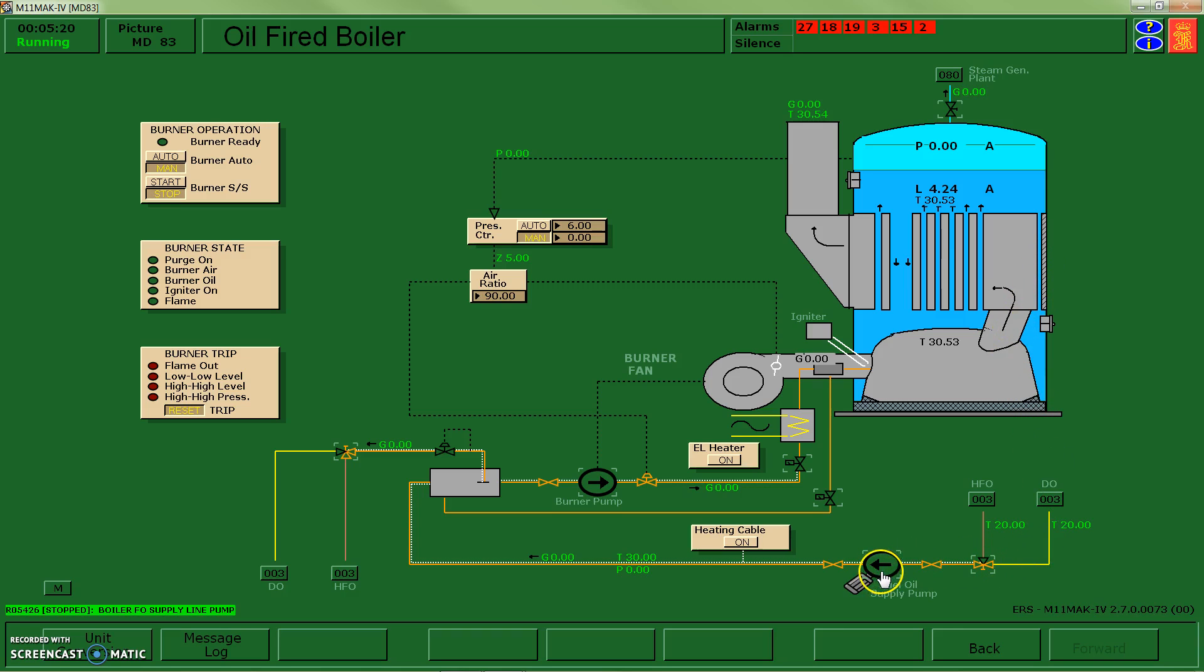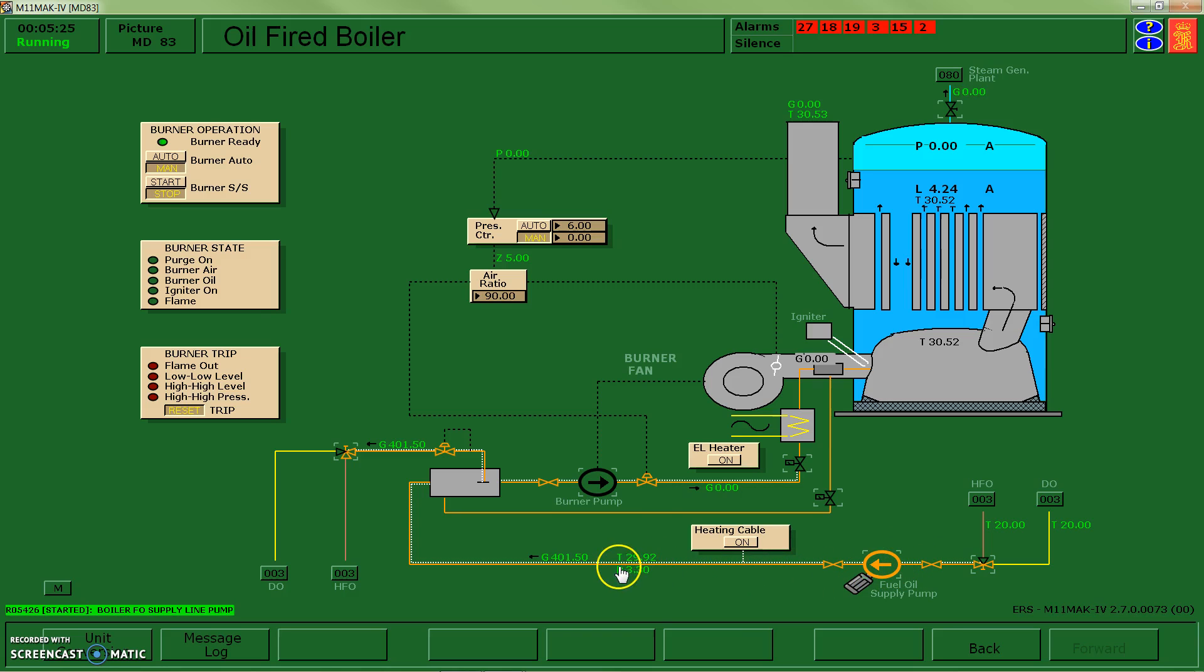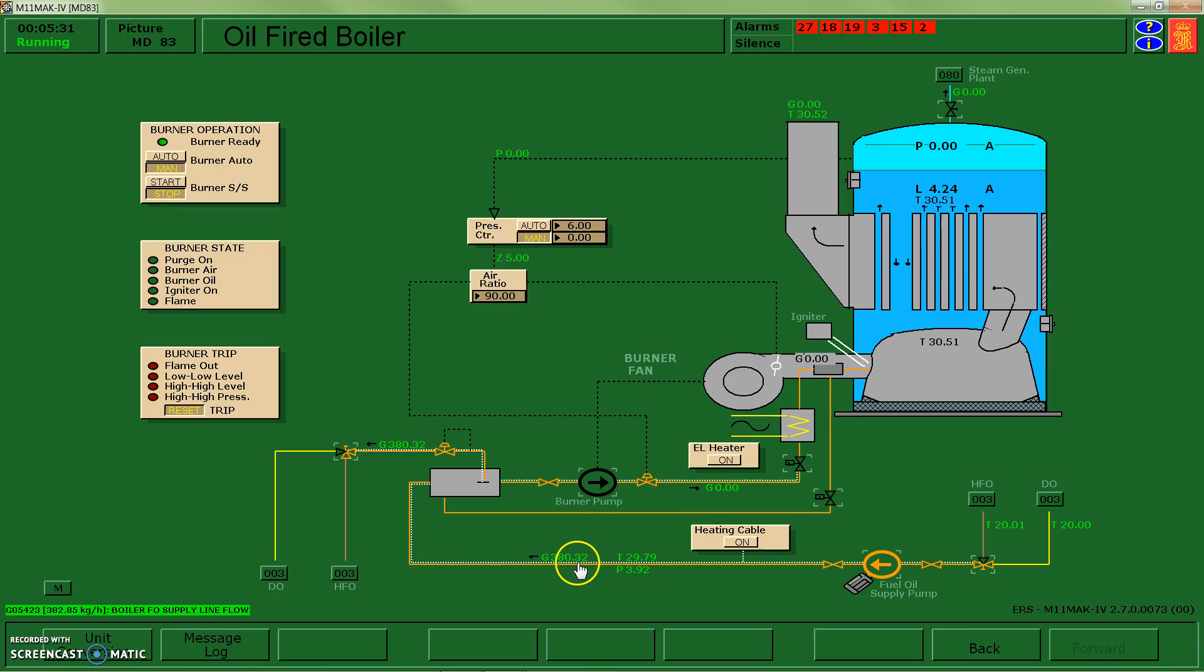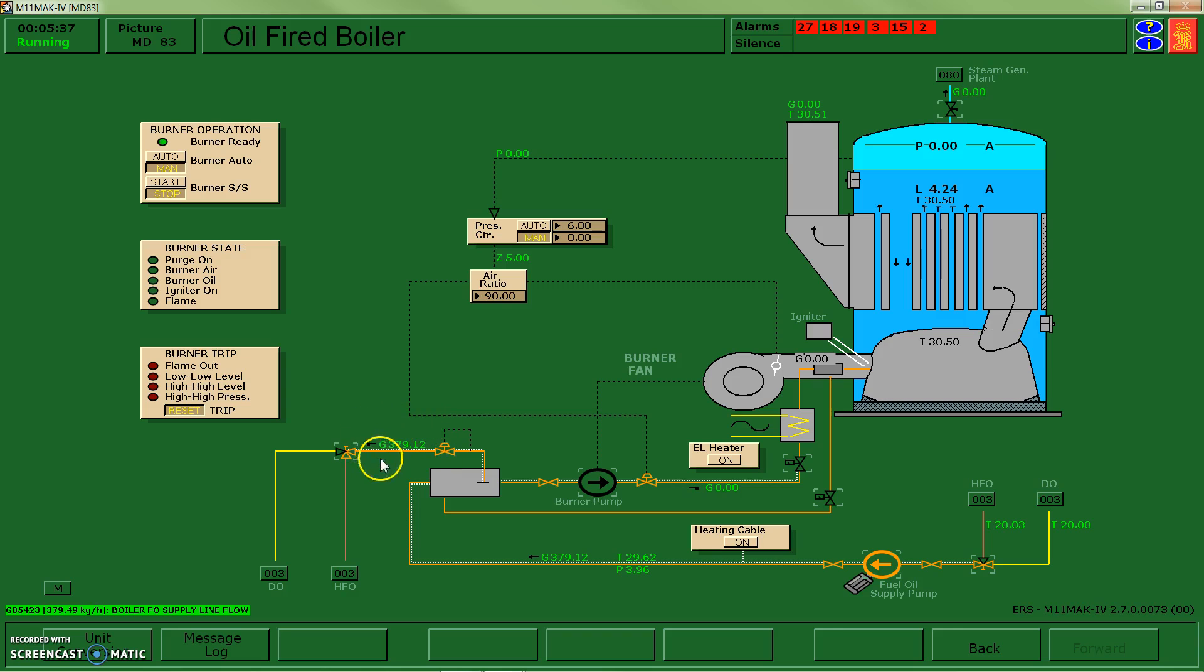In order to get this system to work, I've got a fuel oil supply pump, and when I turn that on you can see that I have some pressure developed and some flow. Right now, because the boiler isn't demanding anything, you can see that all of the excess flow, or 100% of it, gets recirculated back.